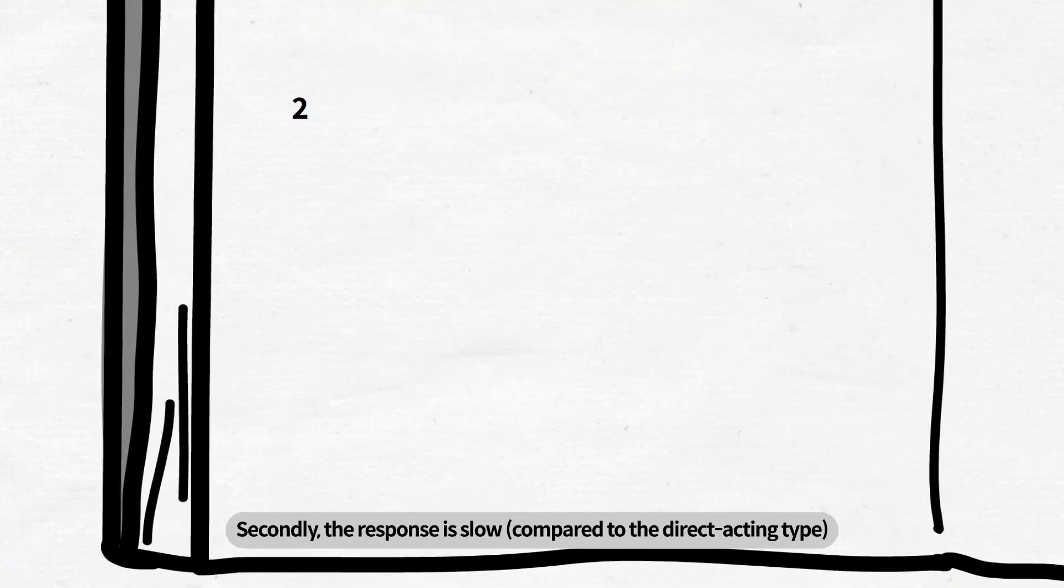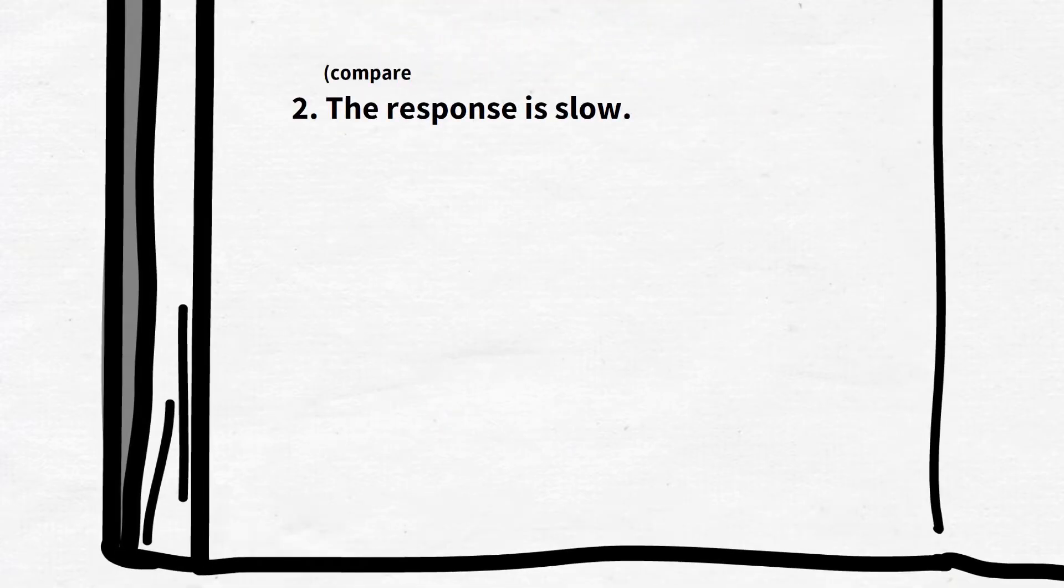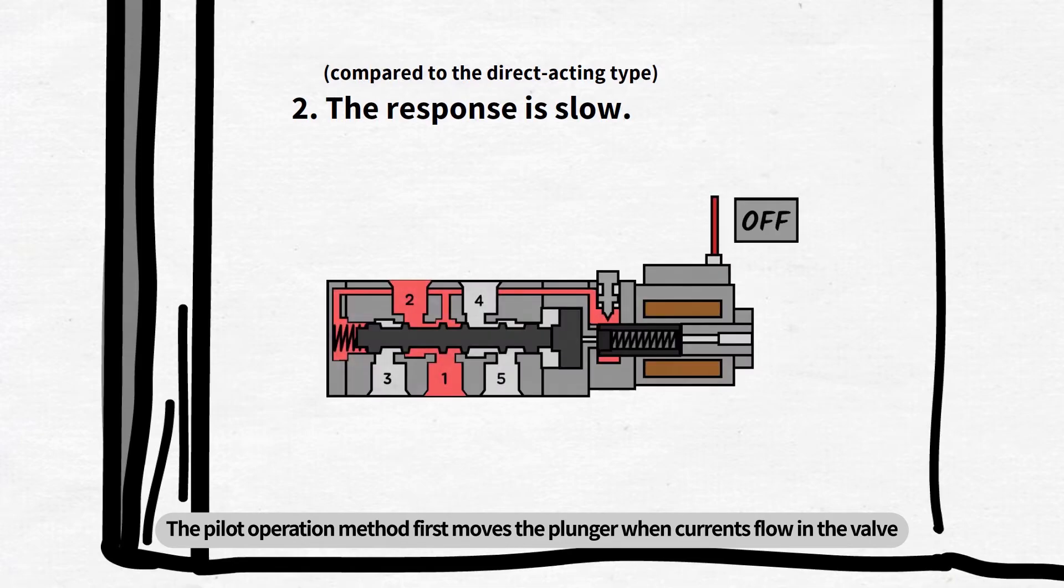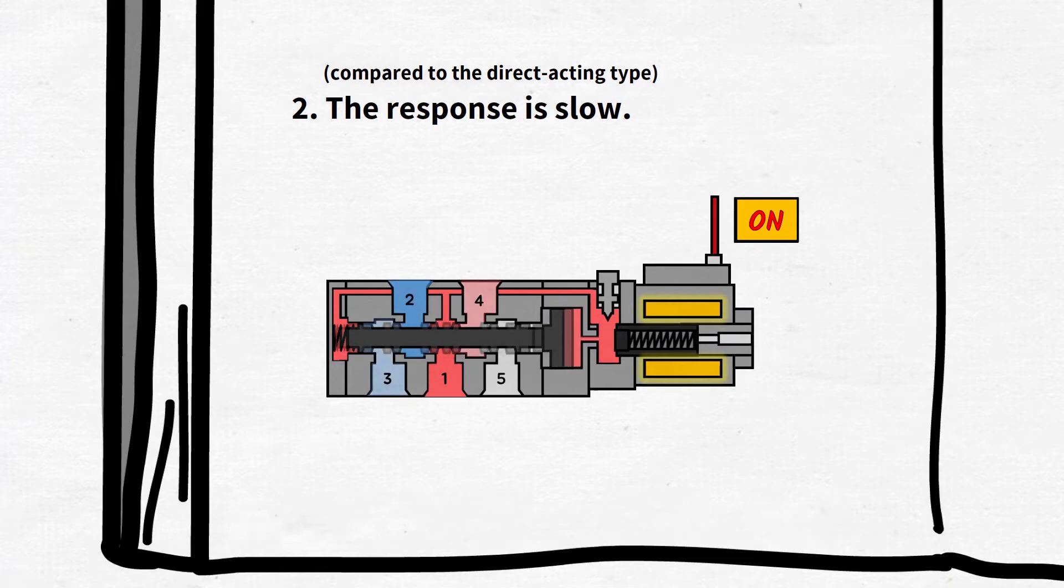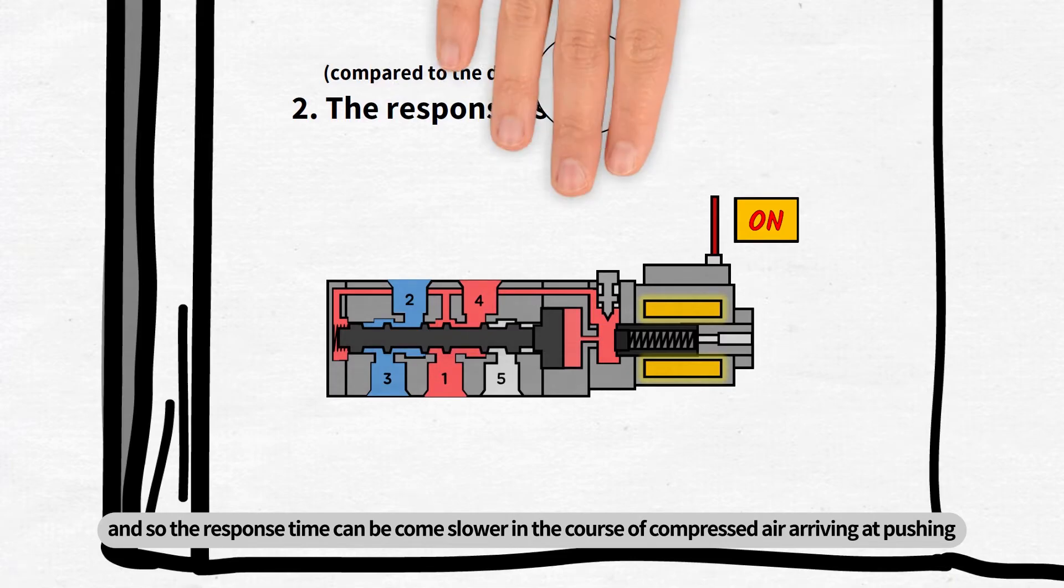Secondly, the response is slow. The pilot operation method first moves the plunger when currents flow in the valve, and then the supplied compressed air pushes the piston and spool. And so the response time can become slower in the course of compressed air arriving at pushing.